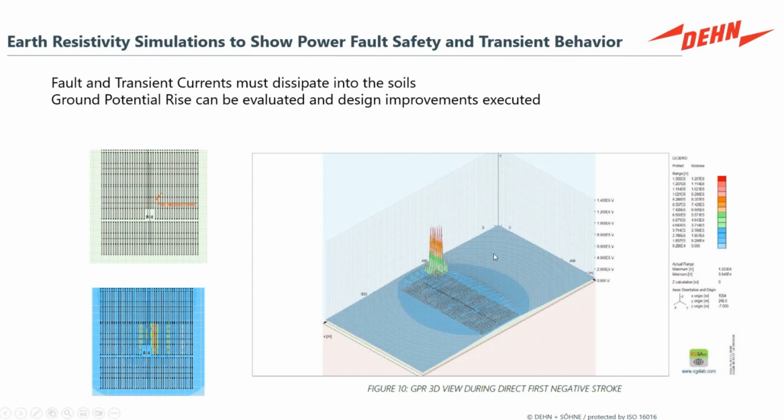So here we're showing a spike with a very high voltage gradient. And what that means is you're getting something like 20,000 volts per meter across your feet or up to the spot you're touching your vehicle around those hotspots. And if the light pole, now picture that light pole out in the middle of a parking lot, is not grounded correctly, if the charging station infrastructure is not grounded adequately, you'll have extremely high hotspots. And the idea behind grounding and bonding is to level it out, smooth it out, so it dissipates more evenly, and you have equipotential grounding, and really the best control of the risk.